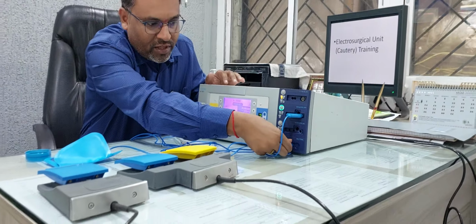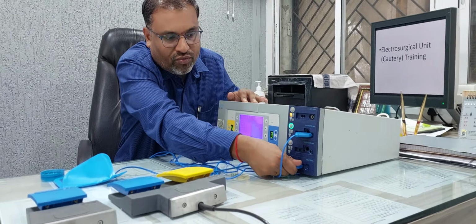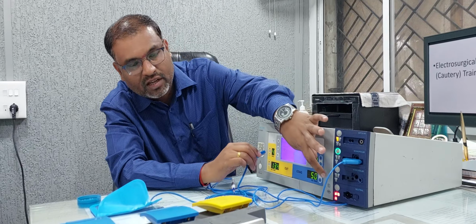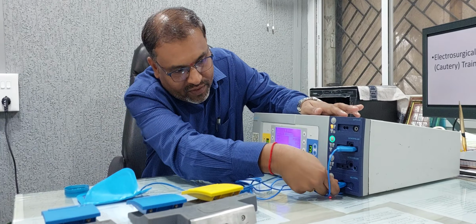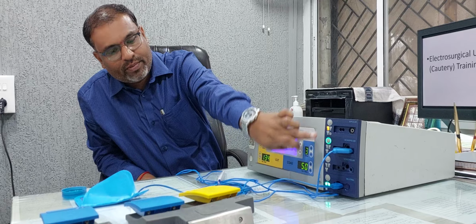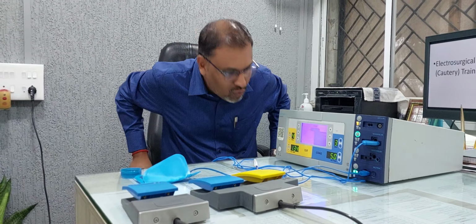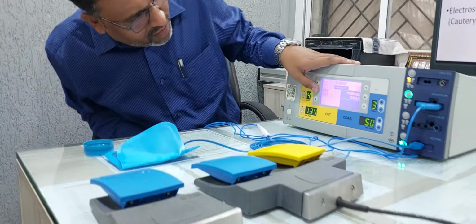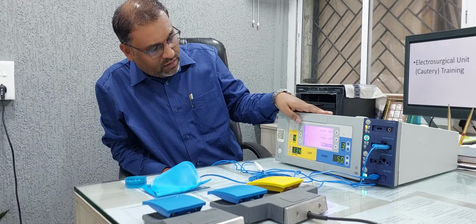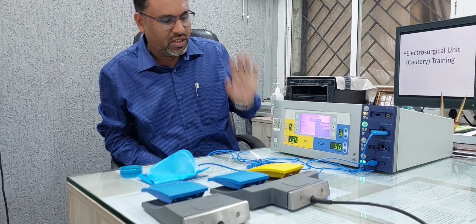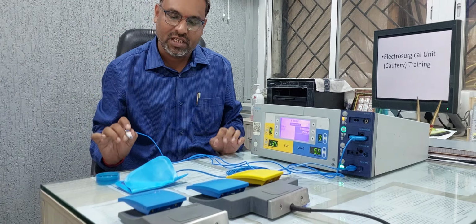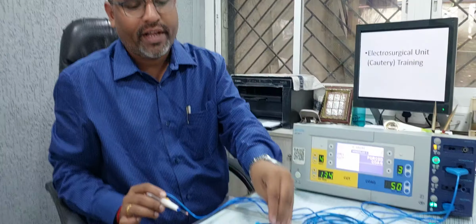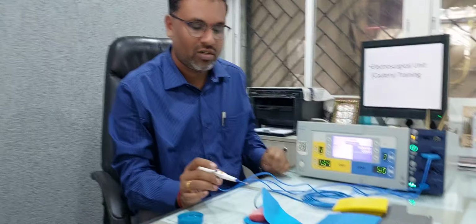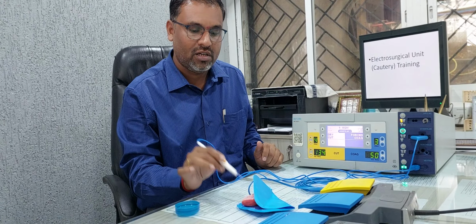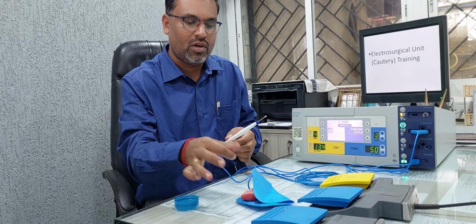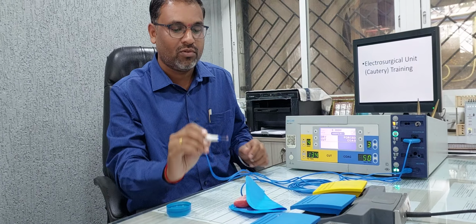And see, if this patient plate is not connected properly, what will happen? It will give the alarm in red color and it will not operate. So always remember, you have to connect it in the proper manner, so it should not be in red color. Now I will show you how to check whether the cautery is working or not, right? Suppose now I just selected any one mode. This is nothing but the pencil. Come close. So what do we have to do? We have to take one soap, hold the cautery paddle, and pour some small water drops on the soap, and I'm going to show you.